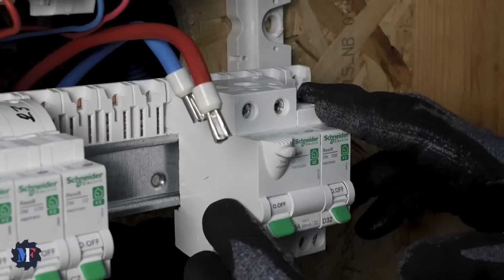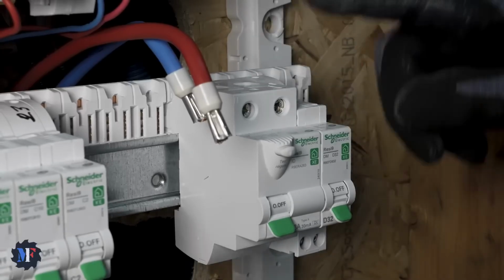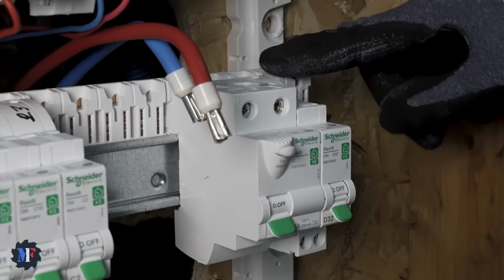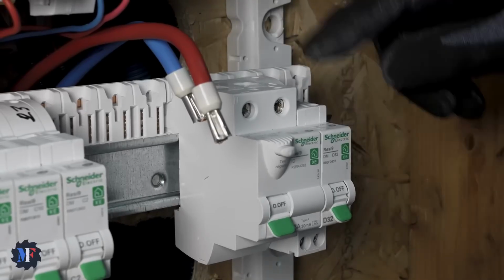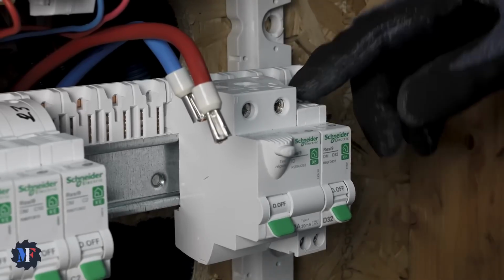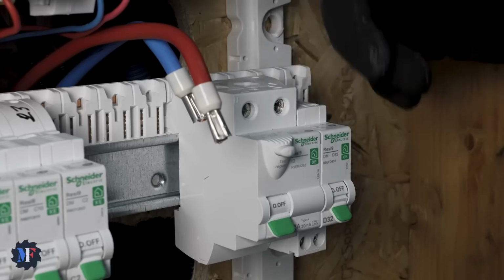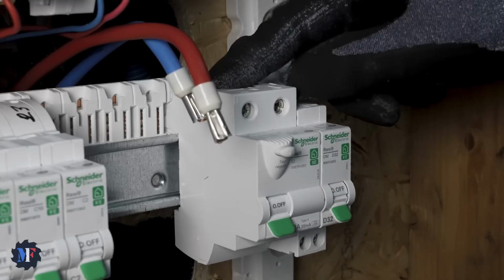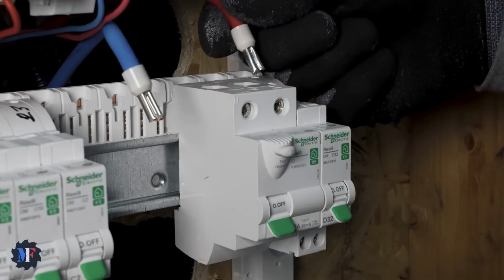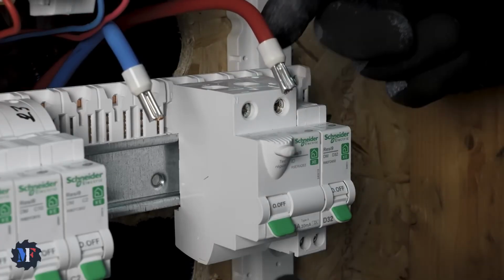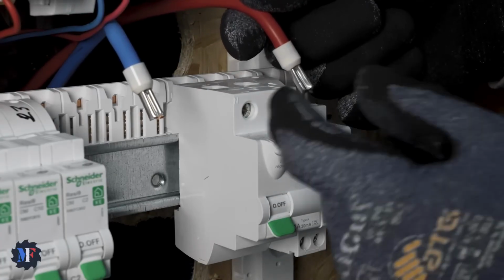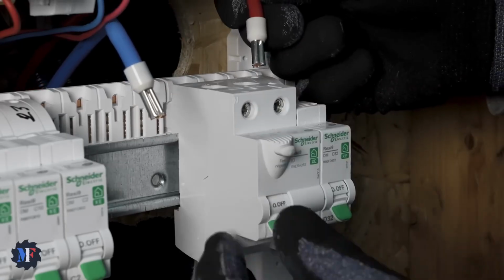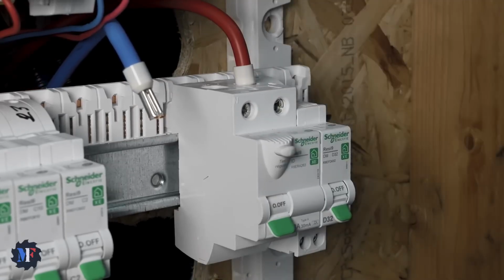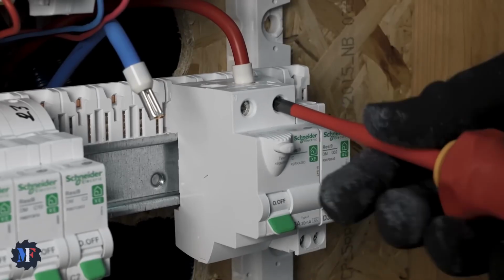To finish with the residual current devices, we just need to connect the one on module 5. Behind it is a 32 amp circuit breaker and above is module 5. I might add a residual current device later or not. For now I'll install a bus bar. I used lugs for now since it's alone, but if I add another above later, I'll switch to a bus bar and remove the lug because, as I told you, no solid wire and no lug with this bus bar system.